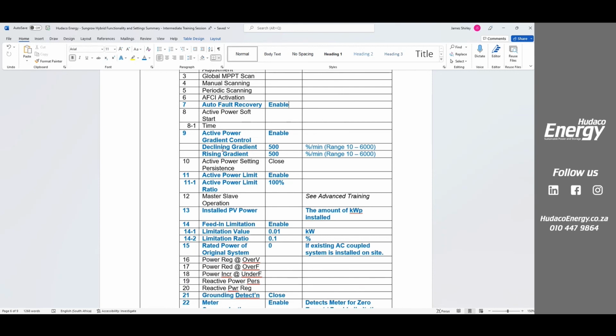So we recommend turning it up from 10% per minute to 100, 200, 500. We can go all the way to 6,000% per minute, right? But then you're that guy in the M3 smashing your accelerator and your brakes. So we don't recommend that. Okay, 500 is normally a good value.